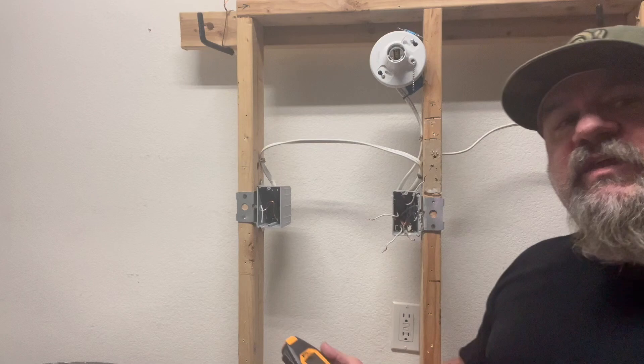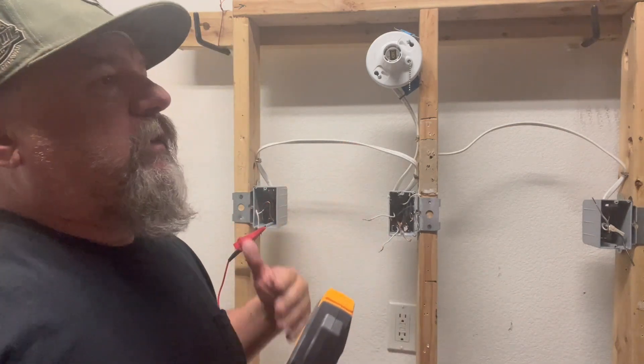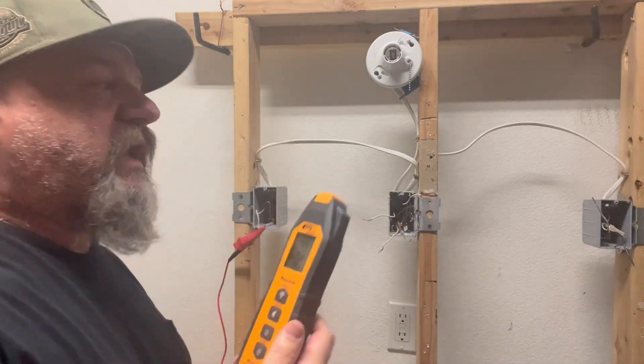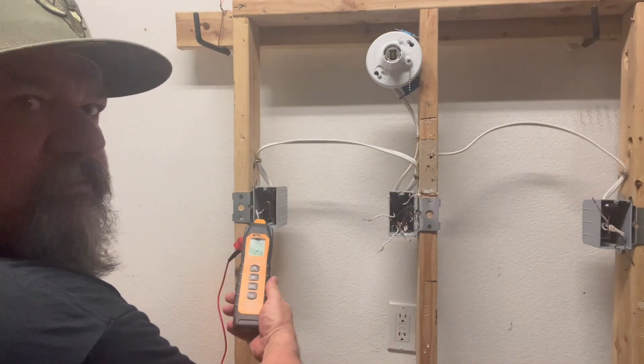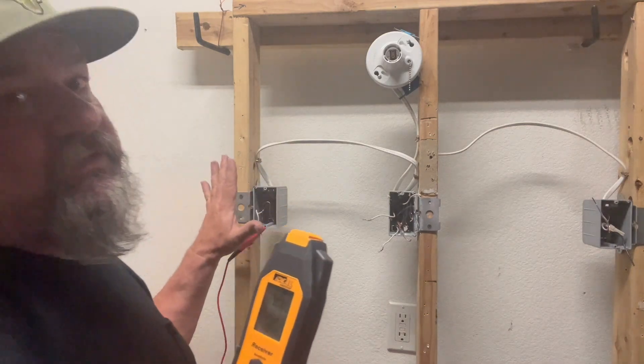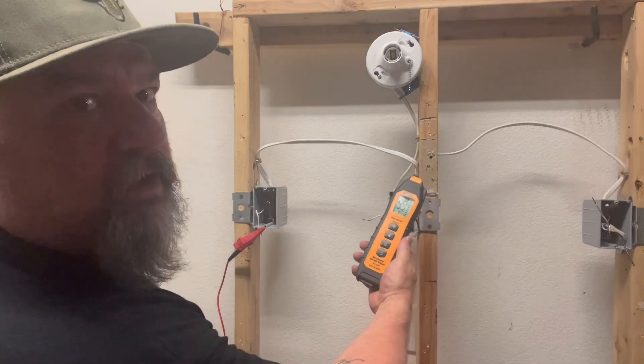We have the transmitter attached to our neutral — there are three neutrals and we're going to figure out which one goes where. We take the receiver to each plug until it starts beeping. See, it's already picking it up — you can see the signal gets stronger as you get closer. It picks up the pulse strongly enough that we don't even have to touch the wire. Found it, and I didn't even have to check all three.